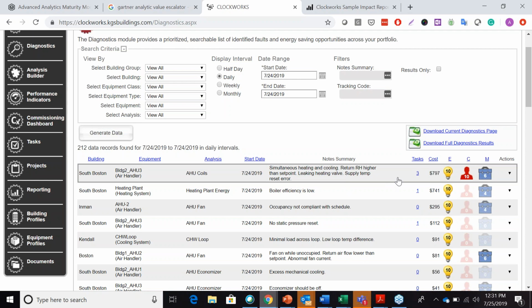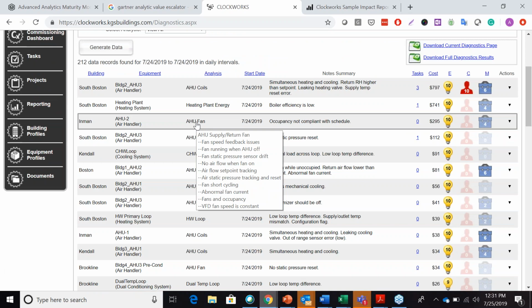By stringing it together, it allows you to get to an accurate cost. So for the fellow energy nerds on the line, I say that term fondly, there should be some appreciation there, right? So the same energy associated with the leaking heating valve is the same excess kBTUs associated with simultaneous heating cooling. So we want to make sure to not double and triple count. That's an important thing relevant to tying these issues together into one hierarchical diagnostic or analysis. So these analyses look for a range of conditions. If you hover over, you see that. And that also provides some positive validation.